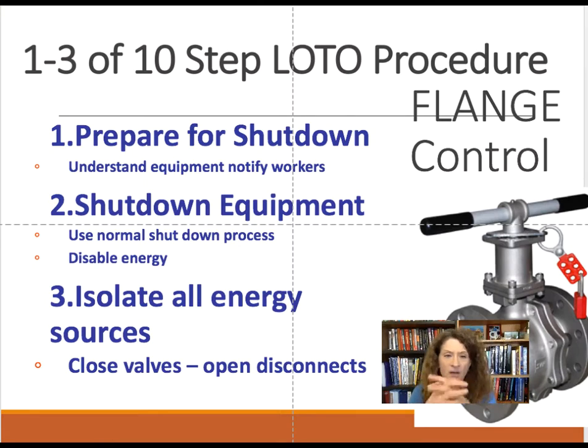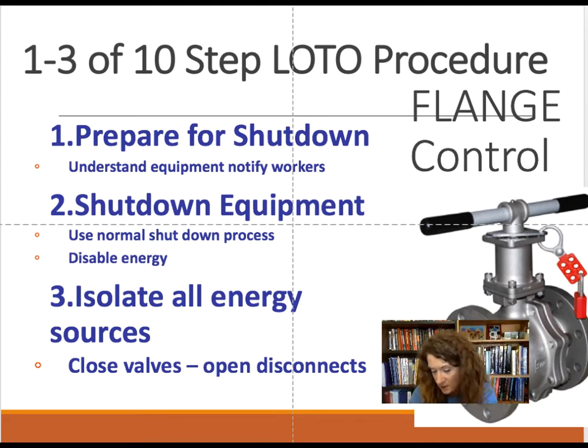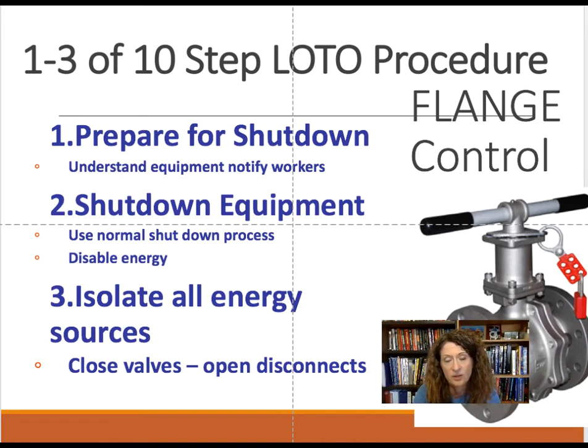There are 10 steps to the lockout-tagout procedure, and it's important they are done in the proper order. Step 1: Prepare for shutdown by understanding the equipment and notifying all people in the area, because shutting down one piece of equipment can affect other areas of a plant. Step 2: Shut down the equipment using the normal shutdown process. Step 3: Disable all energy sources — shut down the power switch, pull the plug, or close all valves and areas feeding into the equipment.